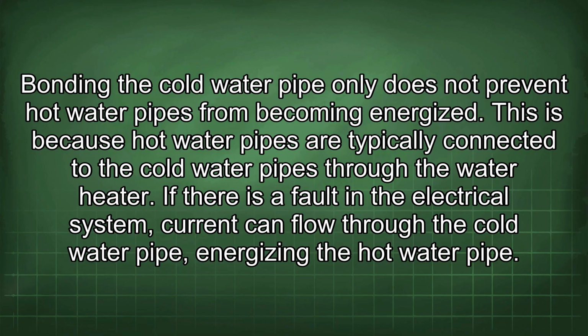Bonding the cold water pipe only does not prevent hot water pipes from becoming energized. This is because hot water pipes are typically connected to the cold water pipes through the water heater. If there is a fault in the electrical system, current can flow through the cold water pipe, energizing the hot water pipe.